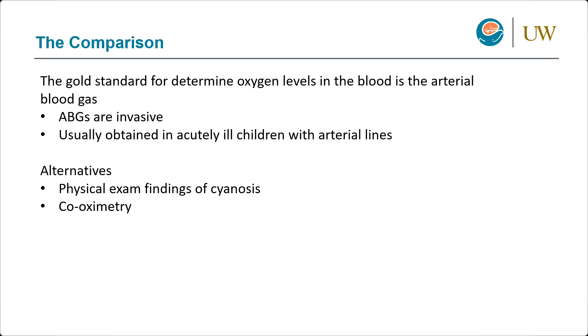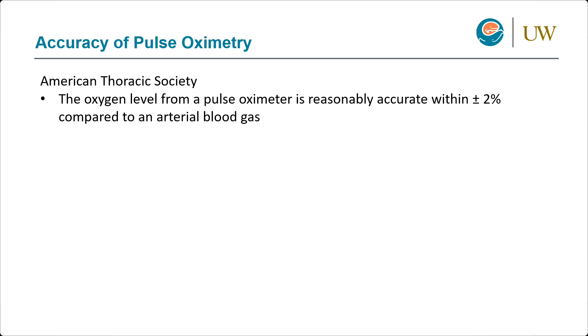And we've been okay with that because for a really long time, we all thought that pulse oximeters were really accurate devices. The American Thoracic Society has a statement that the oxygen level from a pulse oximeter should be accurate within plus or minus 2 compared to what you would get on arterial blood gas. This comes from initial calibration studies done when pulse oximeters were being developed in the late 70s and early 80s. What that means is if your pulse oximeter saturation is 92%, you can think pretty reliably that if I were to get an arterial blood gas, that oxygen level would be somewhere between 90 and 94%.